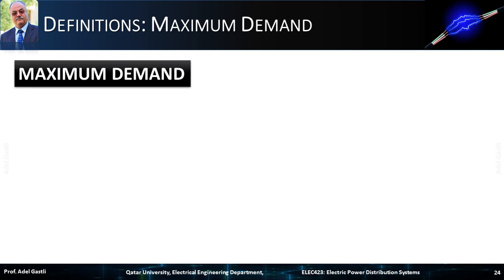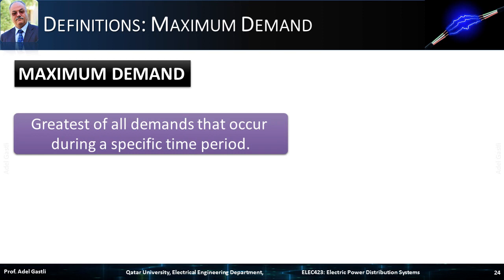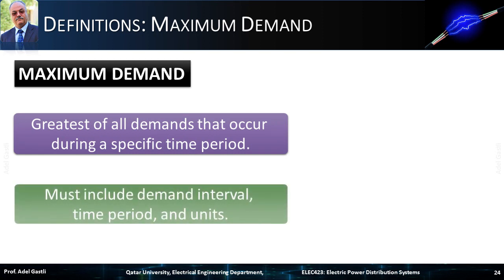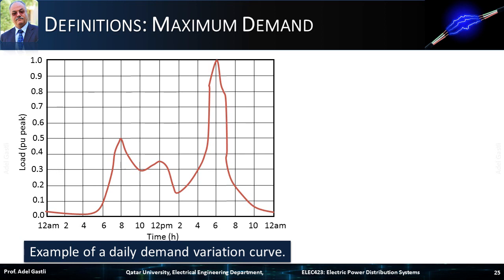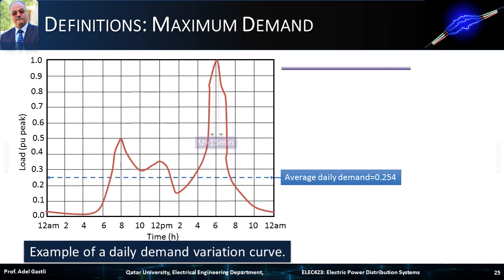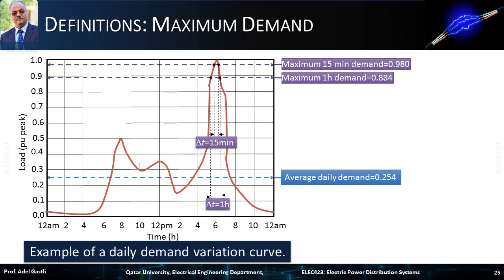Next, let's define maximum demand. It is the greatest of all demands that occur during a specific time period, and it must include demand interval, time period, and units. For example, the 15-minute maximum kilowatt demand for the week was 100 kilowatts. A graph shows an example of a daily demand variation curve where load is expressed in per unit peak. The average daily demand is 0.254 per unit. The maximum 15-minute demand is 0.98 per unit, while the maximum 1-hour demand is 0.884, which is smaller because demand is the load averaged over a specific period — the longer the time, the smaller the average.